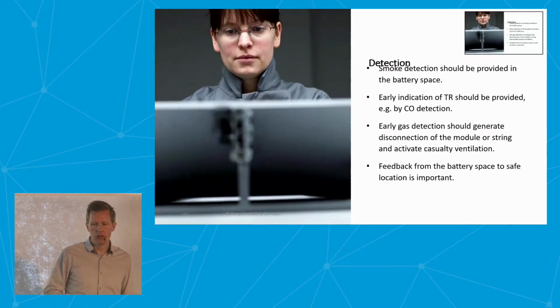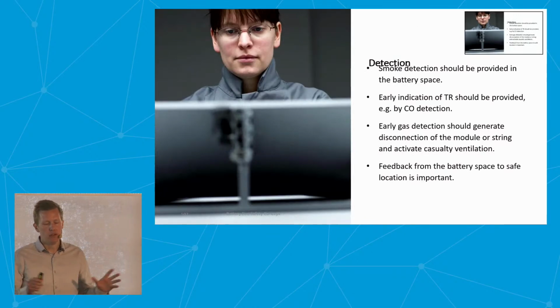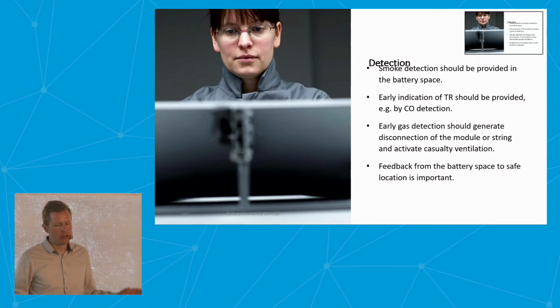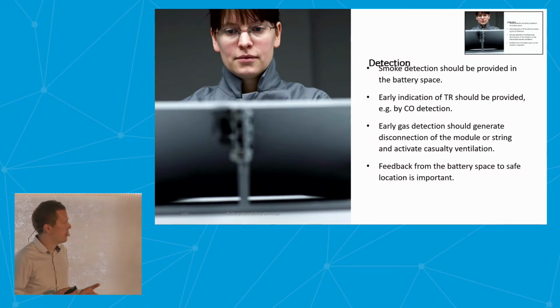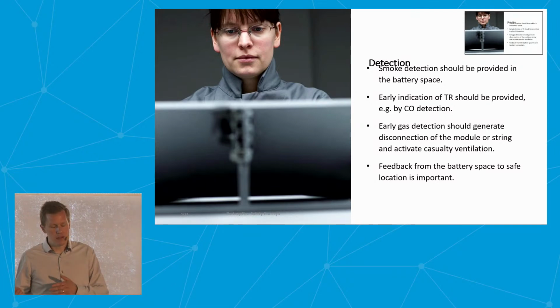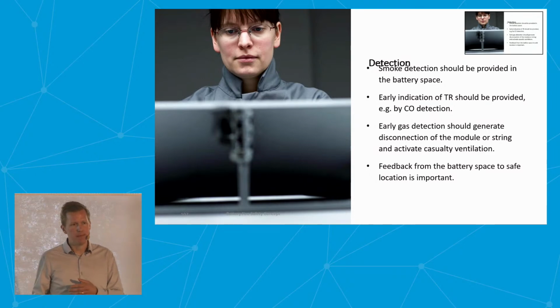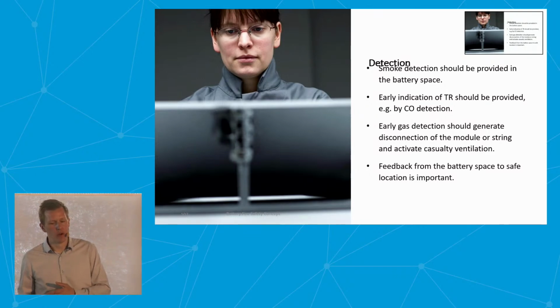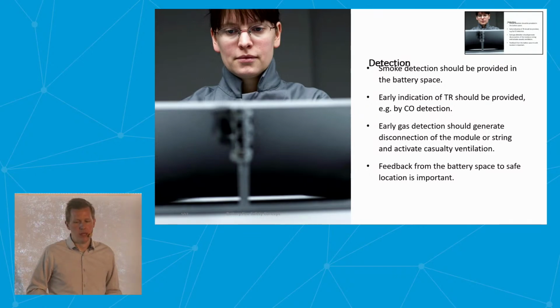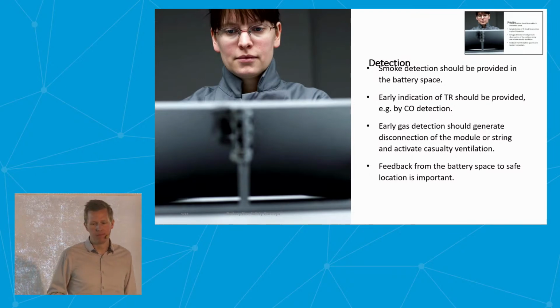When it comes to detection, smoke detection is good as a basis for the room. We think you should also have some early thermal runaway detection closer to the batteries - it could be gas detection. It should be redundant from the battery management system, because the BMS could of course also detect thermal runaway, but you should have redundant systems. It's also important to have feedback in case of an event - you should not go in there, but you should be able to know what is happening.